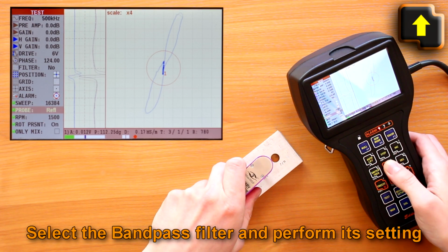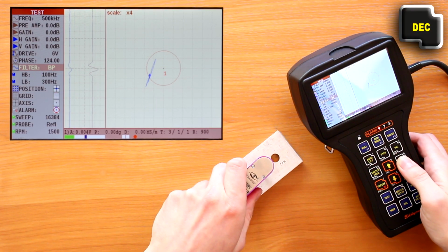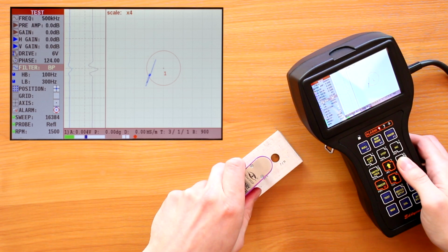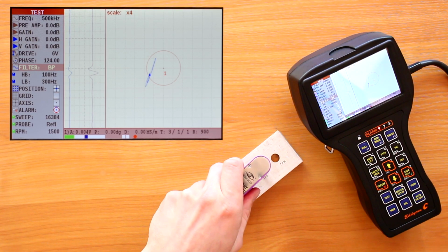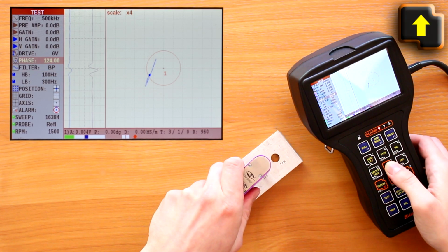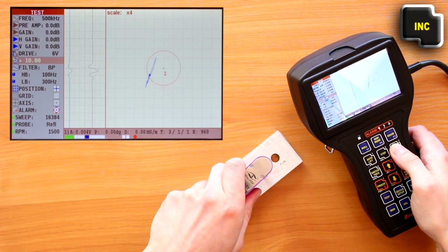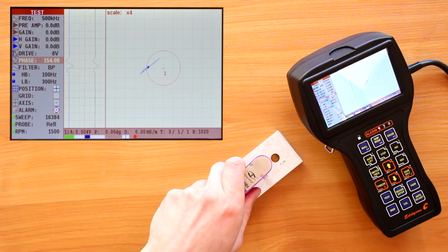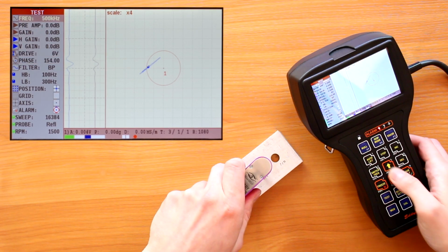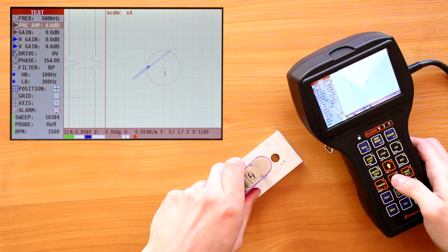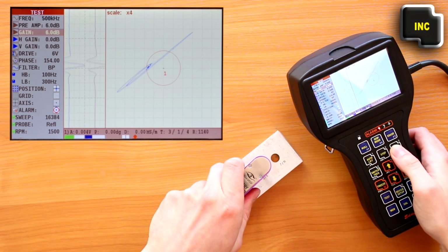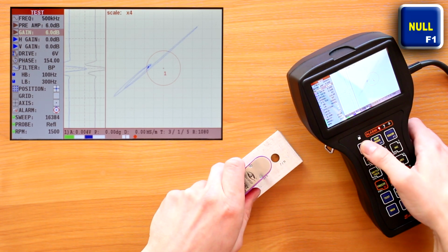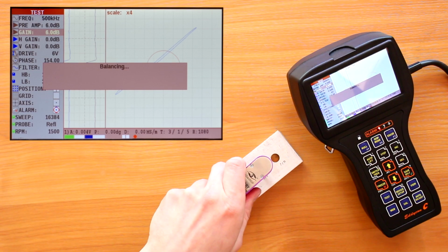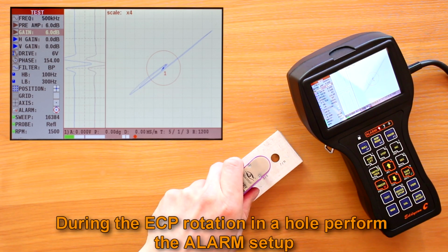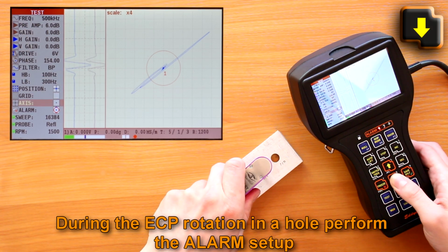Select the bandpass filter and perform its setting. First of all, minimize the distortion signals from the ECP in the hole by setting the LB parameter, and then proceed with the HB setting. You can correct the ECP phase using the phase parameter. While increasing the gain on preamplifier and amplifier, maximize the signal amplitude if necessary. After changing any parameter that affects the absolute value of the signal, it is important to perform balancing by pressing F1. During the ECP rotation in a hole, perform the alarm setup.